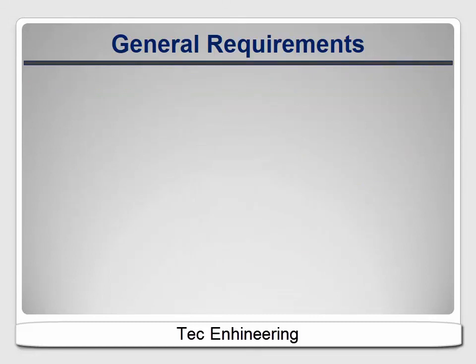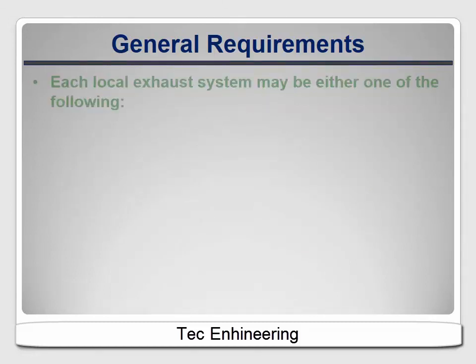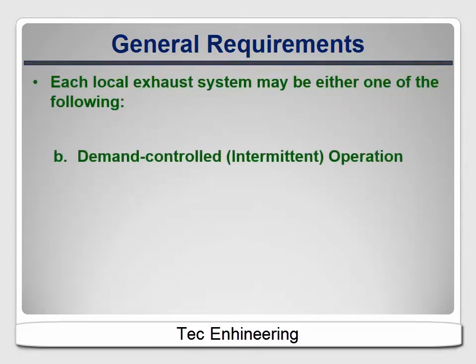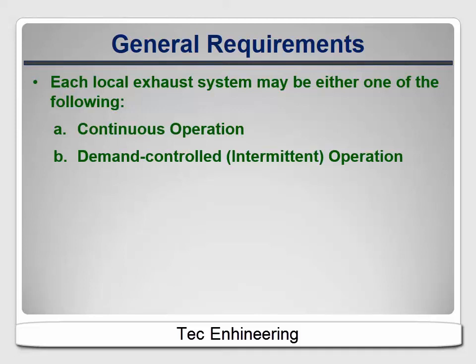The standard gives two options for operation of these systems: demand controlled or continuous. We rarely see continuous systems except in multi-family buildings where a rooftop fan might run continuously to serve multiple apartments below it. One case where a continuous system might be used in a single-family house is if a balanced system like a heat recovery ventilator is installed for fresh air. These are slowly becoming more common and I'll come back to them later in the course.